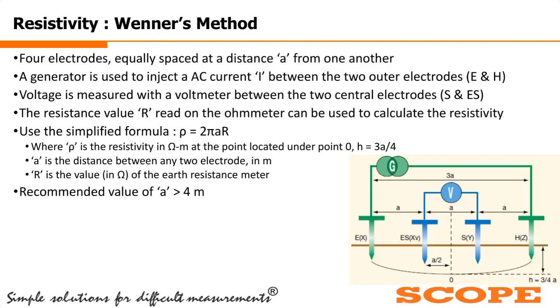So if the distance between the E and ES rods is 5 meters, then the depth is 3/4 of 5. In this way, we have to insert these earth electrodes at a depth of h. With the help of this formula, we can easily calculate the earth resistivity in ohm-meters.